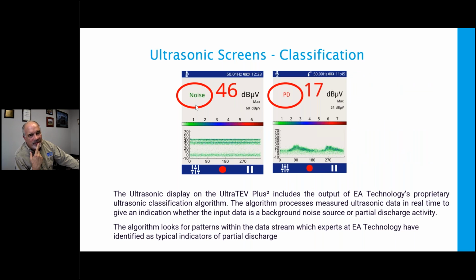Here's an example of a phase resolved plot that is clearly not phase resolved. It's random. It's noise. Even though I've got a level that's 1,000 times worse than this one, I'm much more excited about the one on the left because it says it's PD, and my phase resolved plot looks like PD. This one probably sounds like a high-pitched squeal, so I've got audio telling me no, algorithm tells me no, phase resolved plot tells me no. This is not PD.